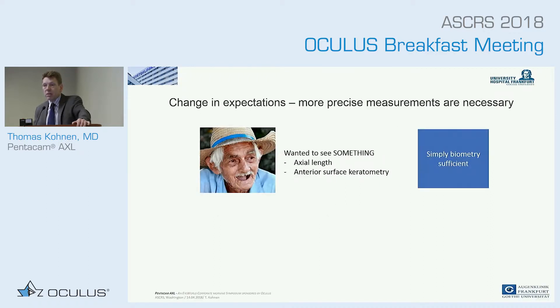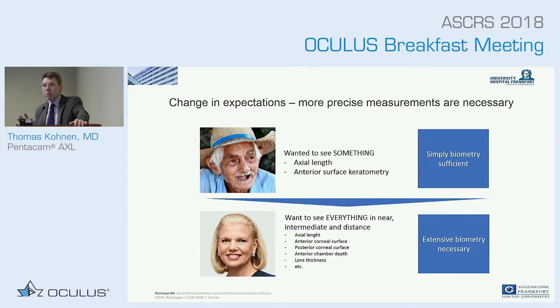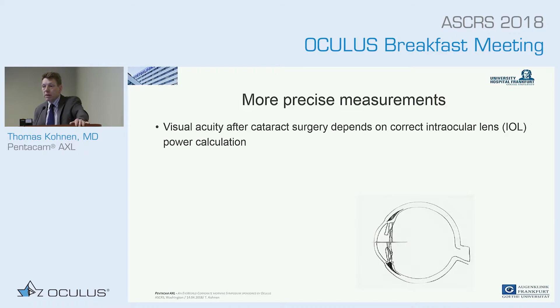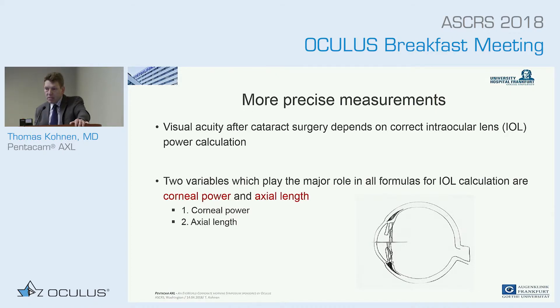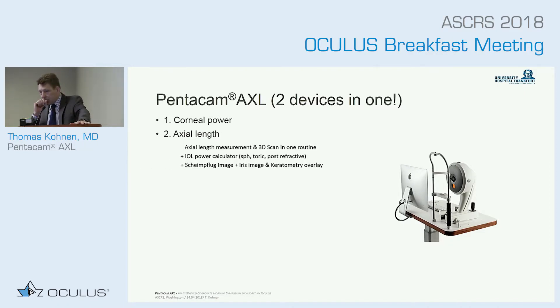The change of expectation in patients is there — more precise measurements are necessary nowadays. From the time when simple biometry was sufficient, I think we have moved into an area where patients, when we're talking about multifocal lenses, want to see at near, intermediate, and distance. If we do measurements correctly, we have better outcomes. For IOL calculation, two variables are very important: corneal power and axial length. That brings us to the Pentacam AXL — two devices in one machine — which measures both corneal power and axial length.